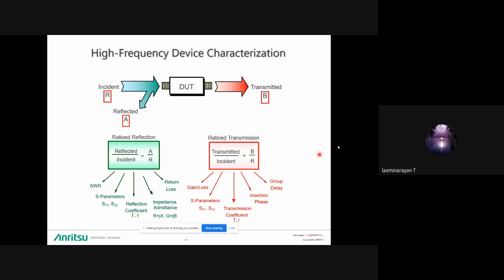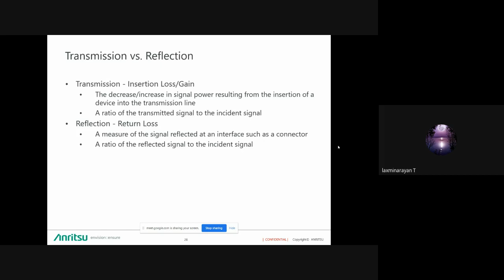And these are some of the parameters which will be measured using network analyzers. So transmission and reflection. Transmission is nothing but transmitting from one port to the other port. During the ratio measurement of an input, incident, and transmission, we will get the gain or a loss. Reflection is nothing but a major parameter, return loss, which measures the signal reflected from an interface such as a connector, or it is the incident signal being reflected back to the same port. So this is called the reflection parameters.